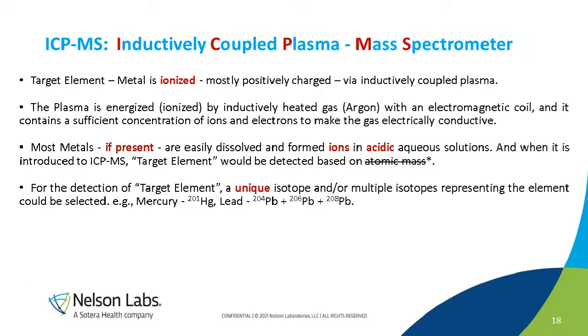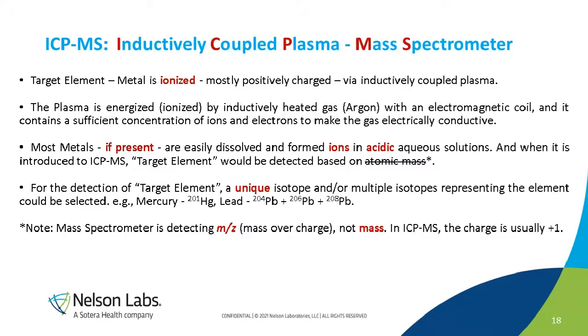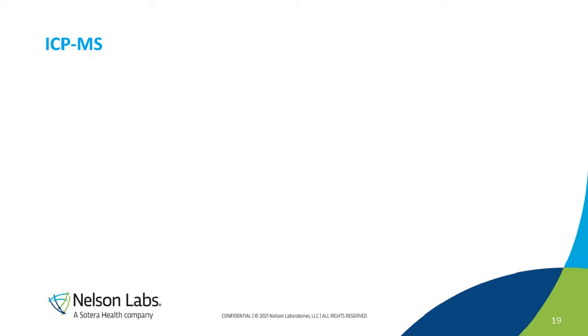Oh, this one I should point out later. For the detection of the target element, we could use a single isotope, something like mercury, atomic mass 201, or we could choose multiple isotopes, something like lead, atomic mass 204, 206, 208, and then combine them together to detect lead. Since I pointed this out before, about this mass spectrometer, I think everybody knows it is not detecting mass, it is detecting mass over charge, m over z. But usually in ICP-MS the charge is +1, so with m over z of +1, we could actually say it detects mass.